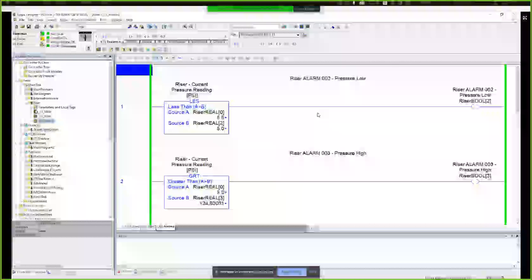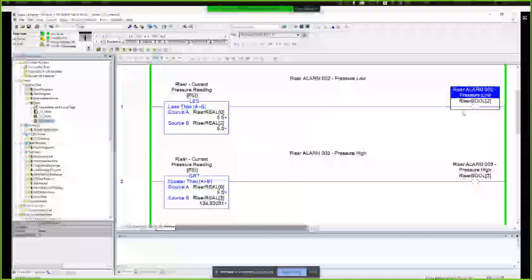So there was a specification sheet that was given to me. I'm calculating the high-high as well as the high limits through a very simple formula. And then there's currently 4 alarms. Like I've mentioned, low-low is going to latch in, the high-high as well. And those 2 are going to require a manual reset from the operator as specified in the sheet. And then the low and high are just going to be essentially lights on the system that are there for pure display.